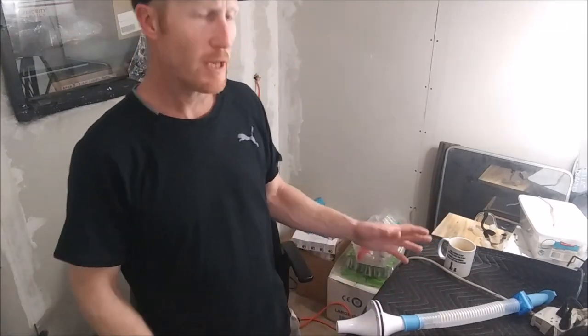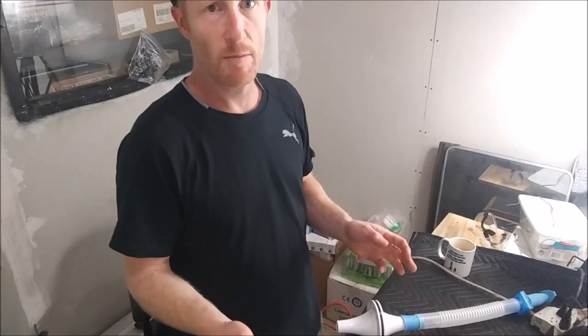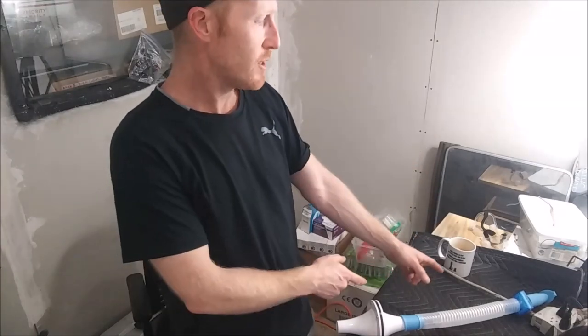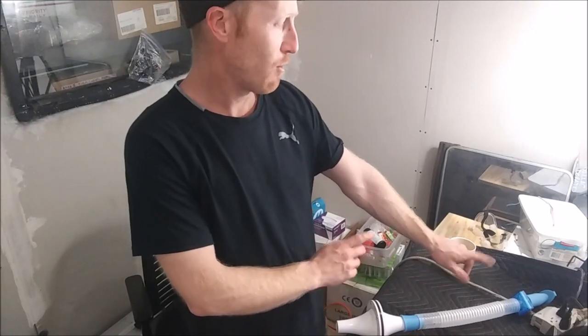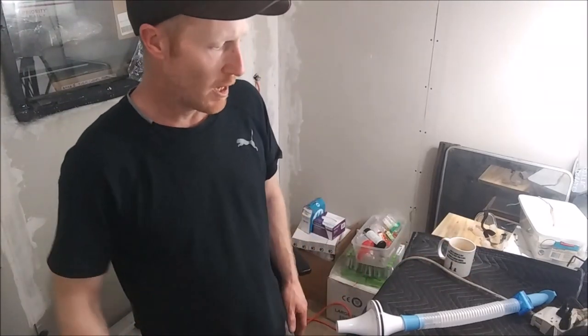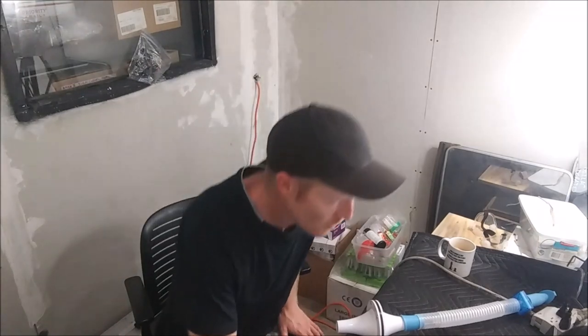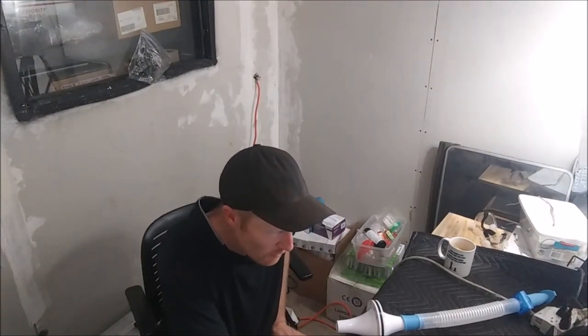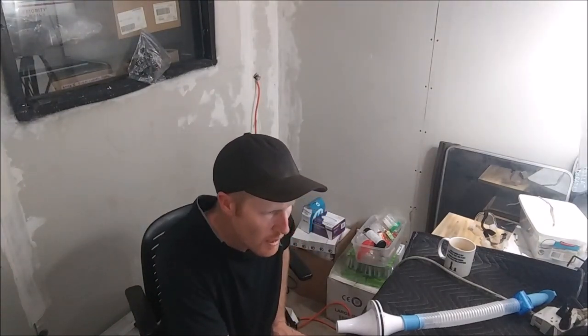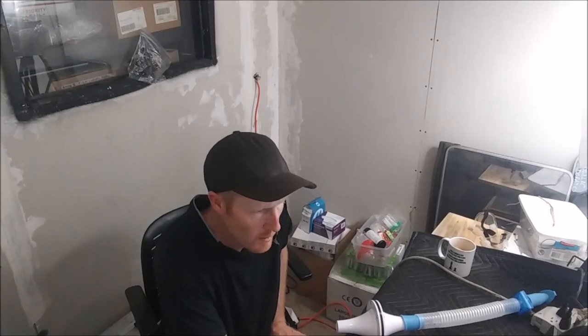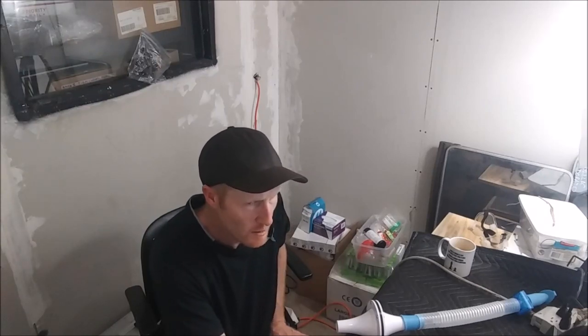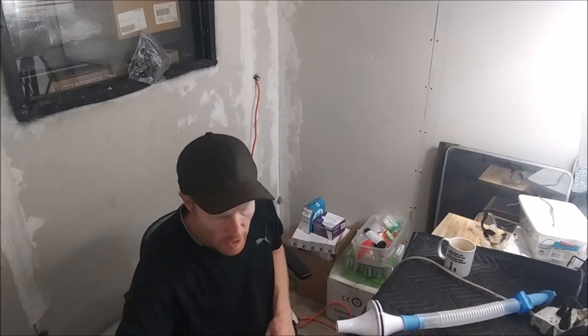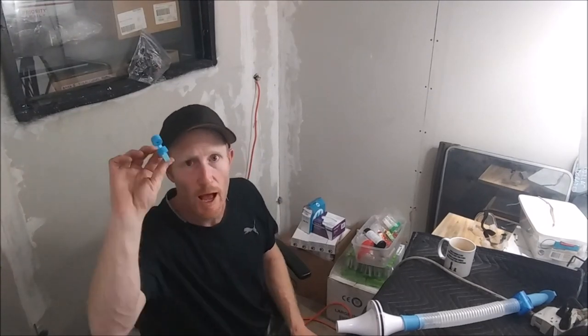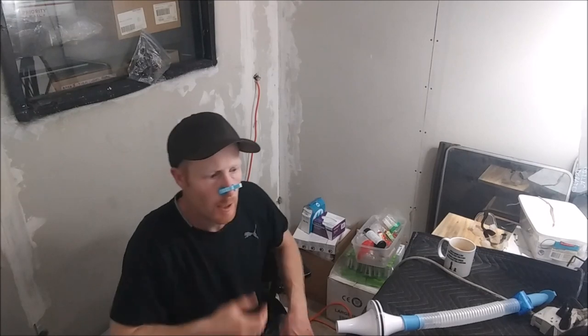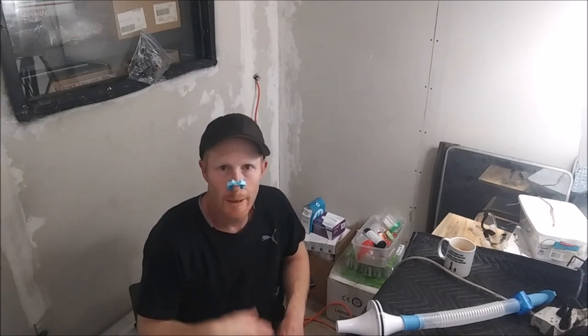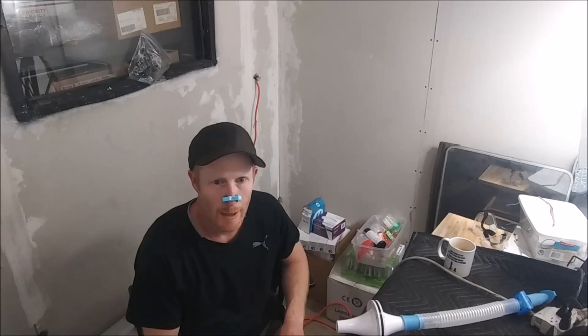The machine's been warmed up for about 15 minutes, and we're just laying the spirometry apparatus right there, not touching it. We're going to start out by going down here on the screen, you'll see it soon, and hitting zero inputs. So we zero the input, and then we can apply our little nose clip and breathe a little bit to get used to it.